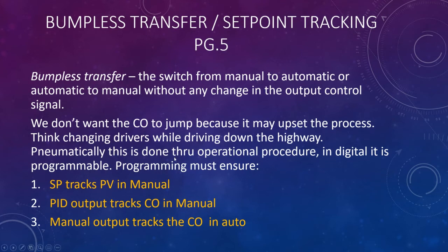Pneumatically, this is done through operational procedure. And those of you who have done some work with pneumatic controllers will know that there's usually some levers and valves. Some of them have little balance beads inside of them where you turn a couple of knobs and you get that little bead to come into the window. And when the bead's in the window, you know that your automatic setting is the same as your controller output.